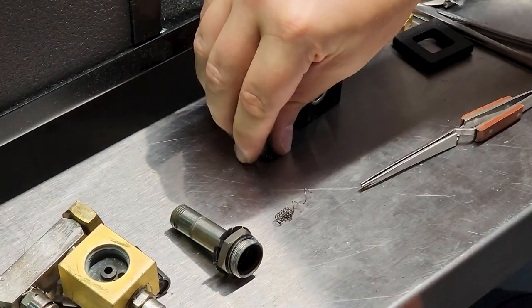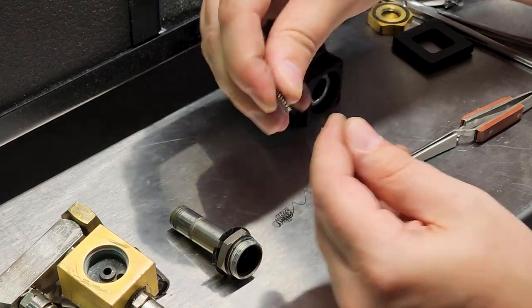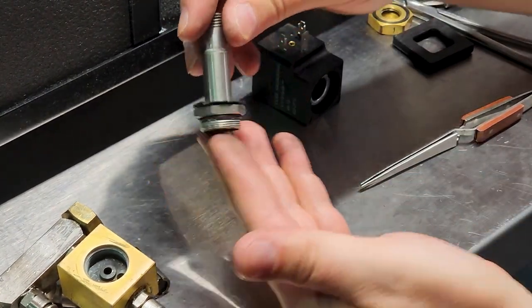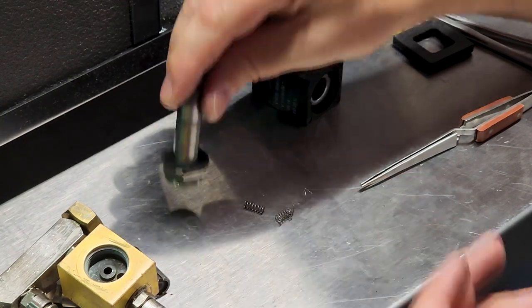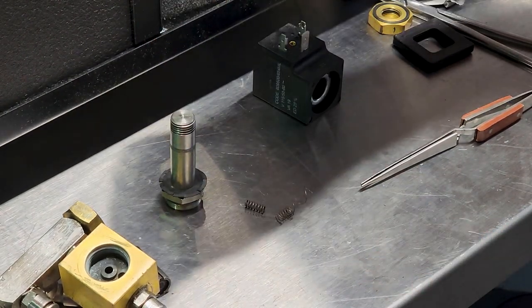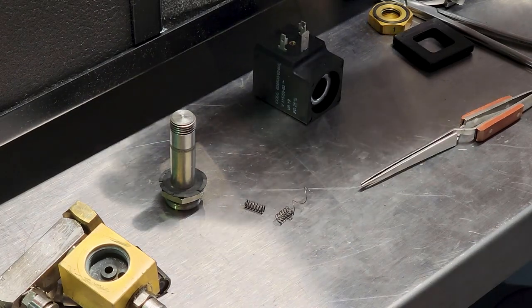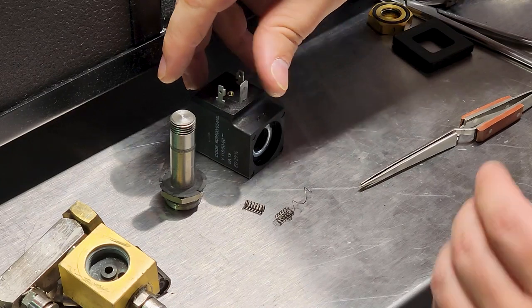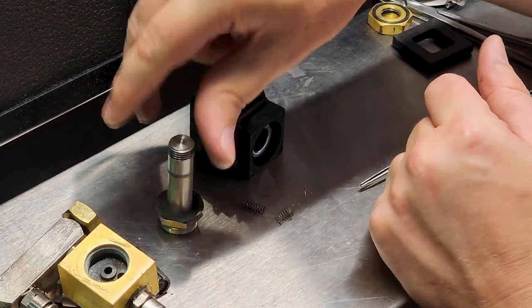It really came down to a bunch of muck inside the valve train, and if that was cleaned out and if this was periodically changed out - like on steam sterilizers there's a regular interval where we change them out - but on devices like these air compressors, we run them to fail. So if you have a buzzy valve solenoid...